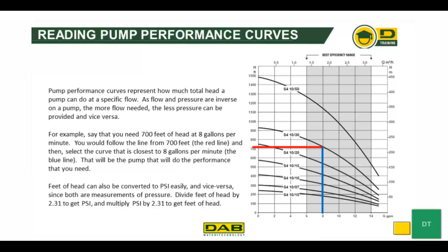Pump performance curves represent how much total head a pump can do at a specific flow. As flow and pressure are inverse on a pump, the more flow you need, the less pressure can be provided, and vice versa. For example, you can see the example here on the right-hand side of the presentation. You would need 700 feet of head at 8 gallons per minute. You follow the line from 700 feet, the red line, and then select the curve that is closest to 8 gallons per minute, the blue line. That will be the pump that will do the performance that you need. This will give you the capability of understanding what performance your pump can do.